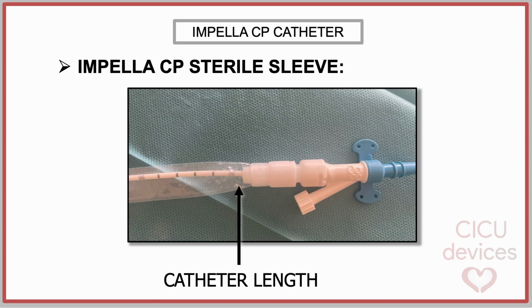At the proximal point of the Tuohy-Borst valve begins the transparent portion of the sterile sleeve. It is at this point that it is advised to measure and document the inserted catheter length, using the centimeter markings imprinted along the shaft. Accurate documentation at the Tuohy-Borst junction is essential for tracking catheter depth, ensuring correct positioning within the left ventricle, and facilitating troubleshooting in case of migration or suspected malposition.